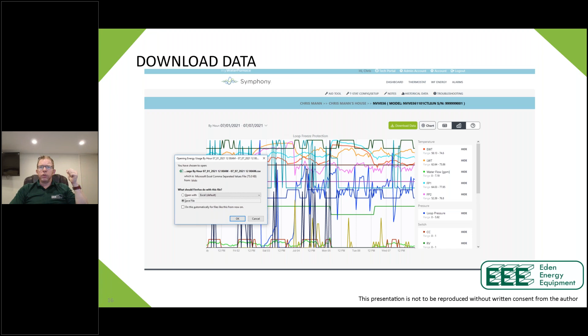The other thing is when we get into troubleshooting faults, in that Excel format look, you have the ability to search for lockouts. For example, if the customer is complaining they're getting communication alerts and don't know what's causing it, we can click on faults and type in whatever the fault may be. So if it's a communication fault, it's an E19. It will bring up the E19 fault so we can look and see what is actually happening there. We could do the same thing with a condensate fault or a freeze protection fault.